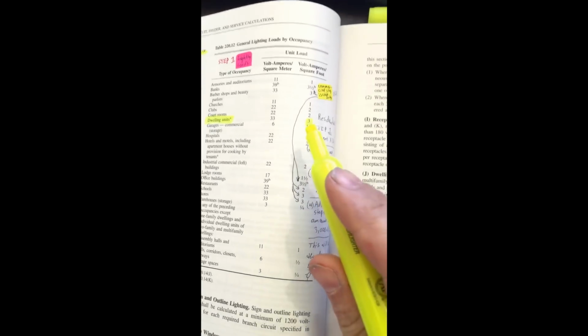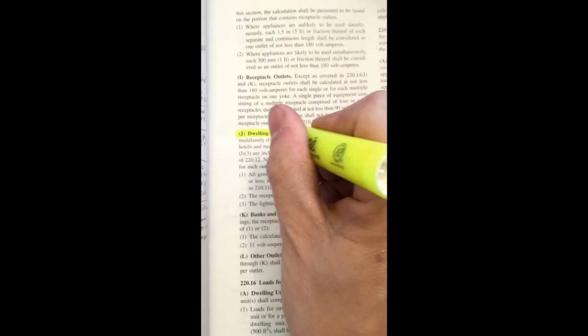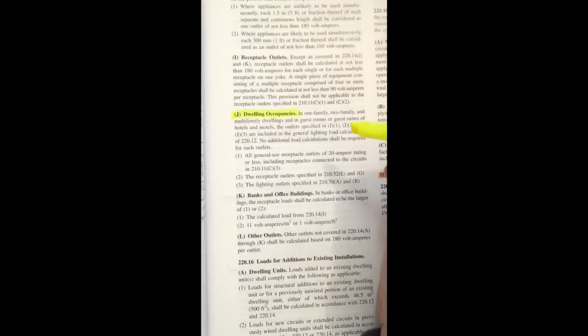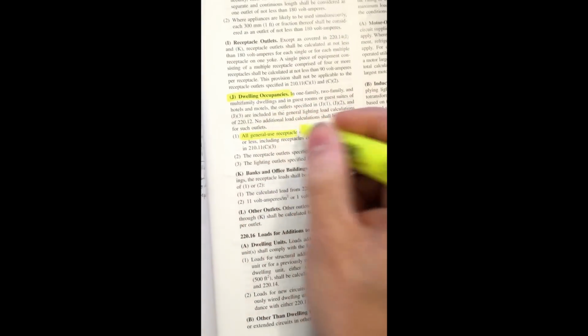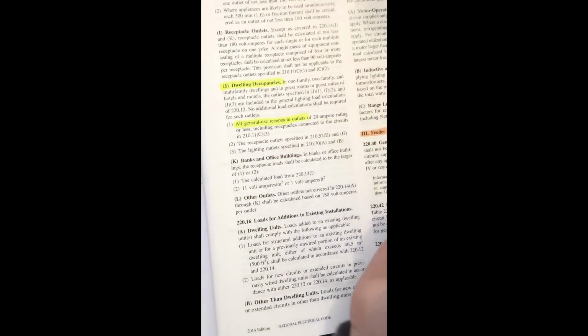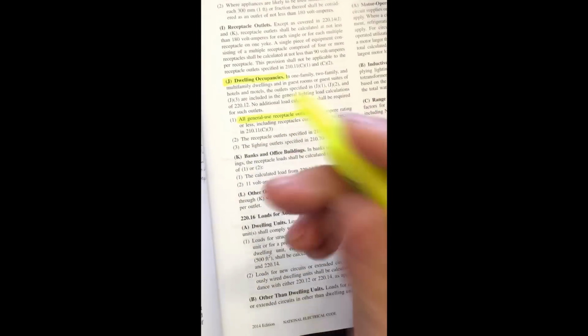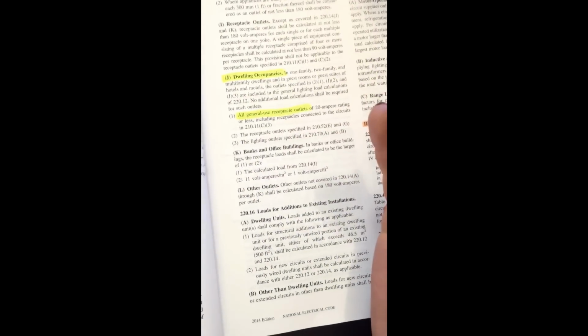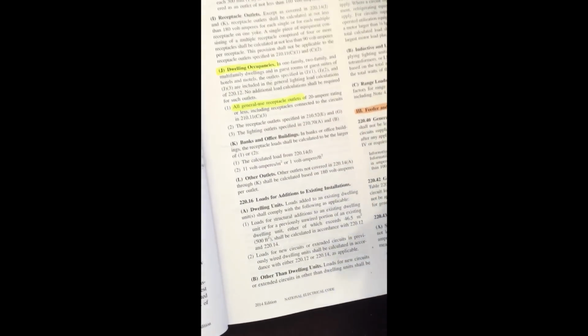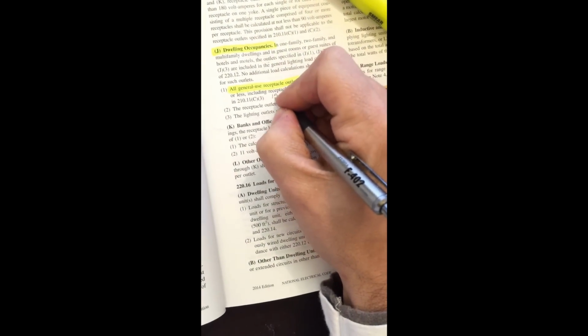All of those are already included in this number right here. And in fact, per code, there's not really any way to separate those. So they're telling us that we've already lumped both our initial steps together when it comes to dwelling units, because we include all of the general use receptacles in that same step. 20 amps rating or less is what it says. However, we differentiate that in the exam world as these are basically the 15 amp plugs.